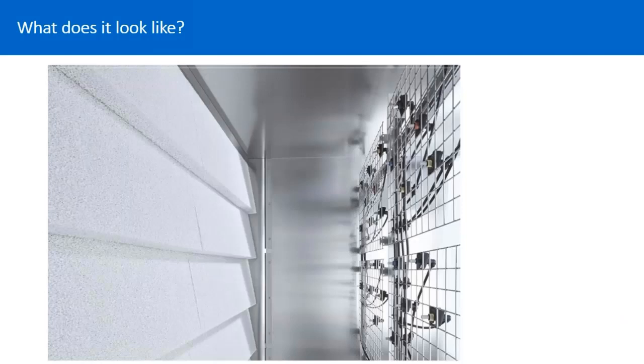What does it actually look like? So this is the combined technology I was talking about. It's called the Condair Dual. It sits inside the air handler. It has a ceramic media and then a pressurized nozzle spray that sprays onto this. So this is certified for a whole variety of hygiene standards so that we know this is very safe to use in healthcare and office space and anywhere you need to make sure nothing is growing in your air handler, which, to be honest, is everywhere if you have an air handler. So this is our preferred system for evaporative in-duct technologies, and then of course we can do it in space with a high pressure system instead. But this is what that would look like inside your air handler.